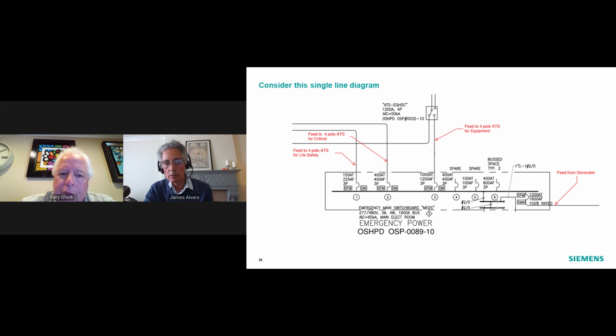We look at the board differently for healthcare than we do in the commercial world, because from a hospital perspective, everything is emergency. And we actually use the term essential electrical system for these generator distribution switchboards. And the categories are going to be different. Just taking a quick look at the switchboard, we've got the incoming feed from the generator. We've got feeds going to what's termed life safety, a feed going to critical and a feed going to equipment. There are also some spares and spaces that have been identified by the engineer.